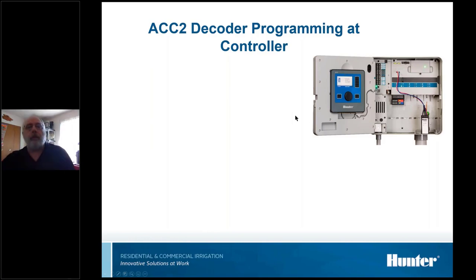Okay, as far as programming on an ACC2 controller, one of the things you'll see that's different about the ACC2 is that the programming port is not on the module like on the rest of them. It's up on the main panel. But it's still the same setup. We're going to put the red and blue wires in the holes, and on all of these, it does not matter which wire goes in which hole. Just red in one and blue in the other.